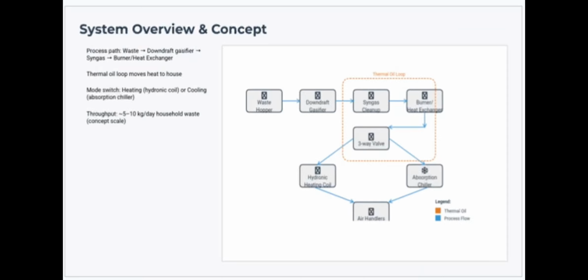Basic breakdown is process path: waste, downdraft gasifier into syngas, and then into the burner/heat exchanger. Then a thermal oil loop moves to heat the house. Mode switch: heating with a hydronic coil and/or cooling with an absorption chiller. Throughput is 5 to 10 kilograms a day of household waste on average.